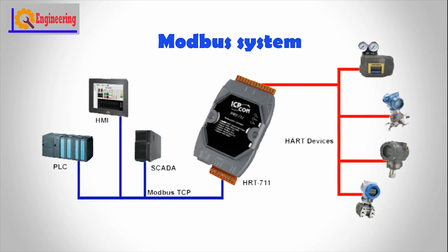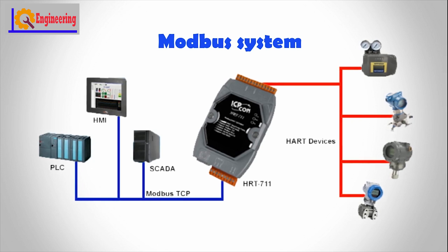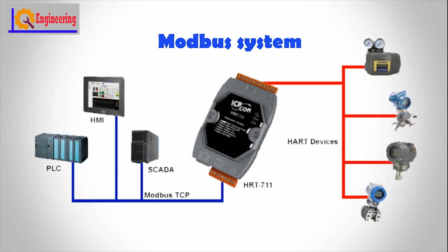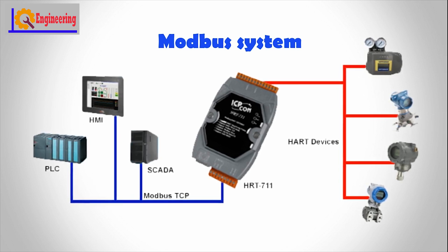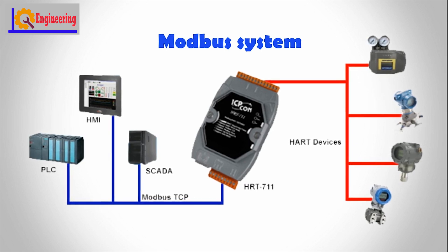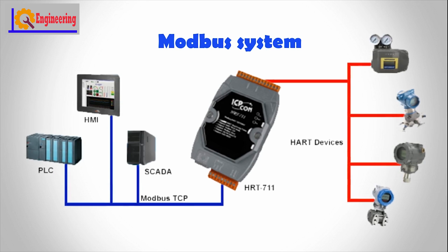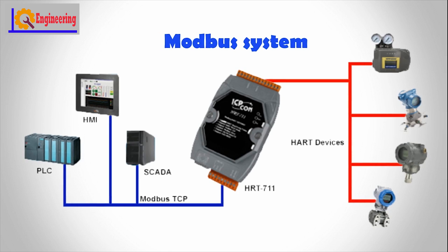How does Modbus work? Modbus is transmitted over serial lines between devices. The simplest setup would be a single serial cable connecting the serial ports on two devices — a master and a slave. The data is sent as a series of ones and zeros called bits. Each bit is sent as a voltage: zeros are sent as positive voltages and ones as negative. The bits are sent very quickly; a typical transmission speed is 9600 baud (bits per second).